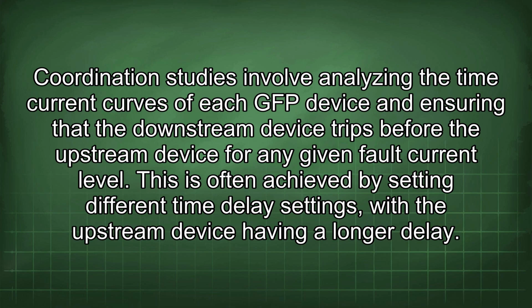Coordination studies involve analyzing the time current curves of each GFP device and ensuring that the downstream device trips before the upstream device for any given fault current level. This is often achieved by setting different time delay settings, with the upstream device having a longer delay.